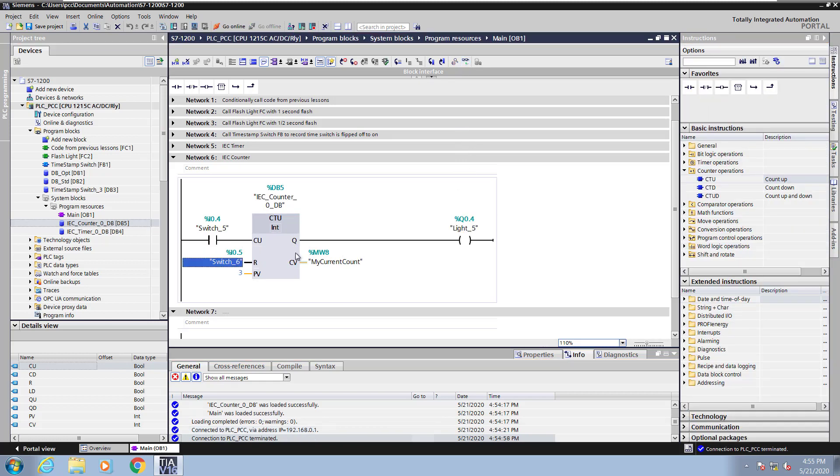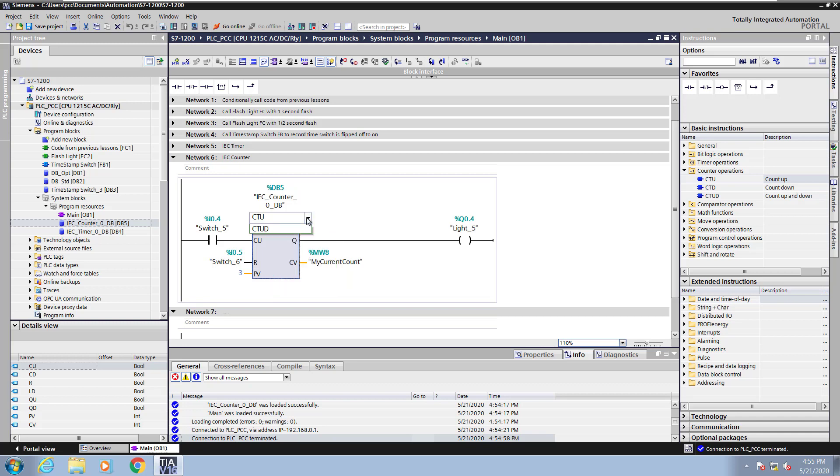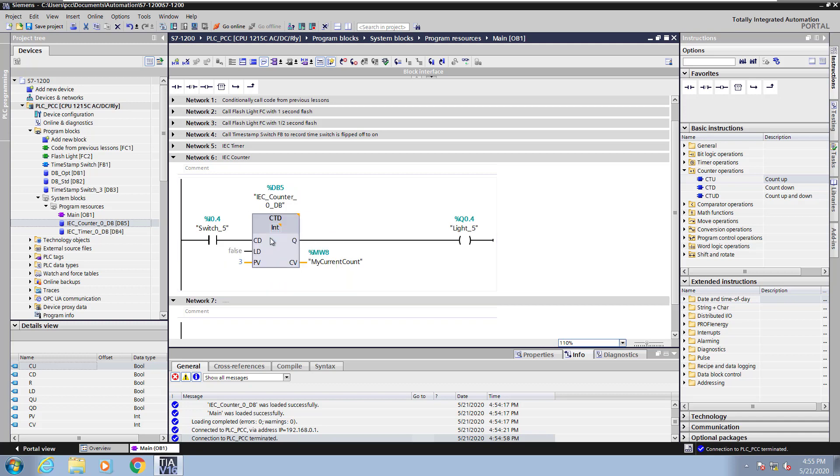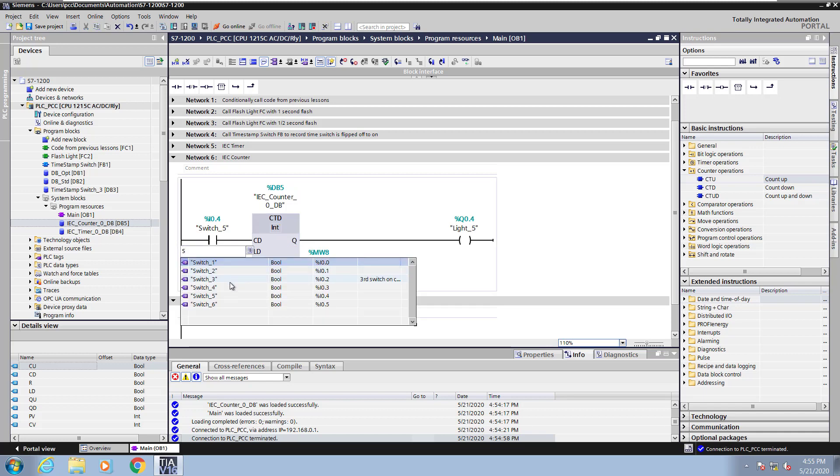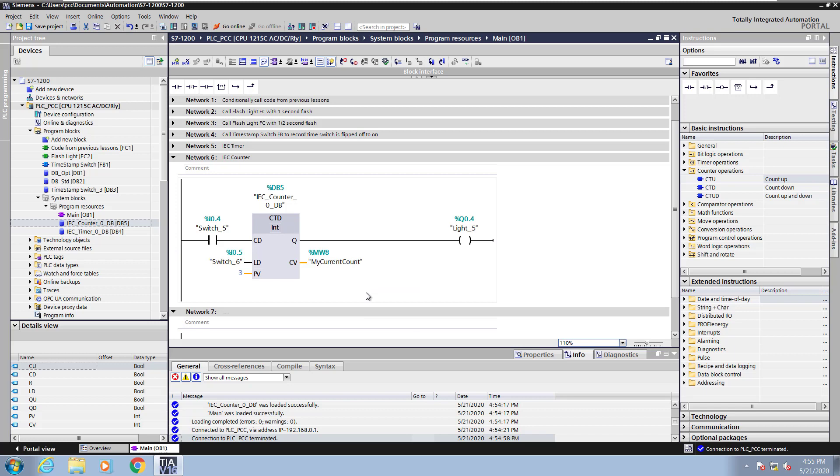I will select the CTU instruction. I can change the data type from int to a different data type if I wanted to, but I am going to leave it as an integer and just change it from a CTU to a CTD and make it a countdown instruction. For the load parameter I will select switch 6. This will load the preset value into the current count.